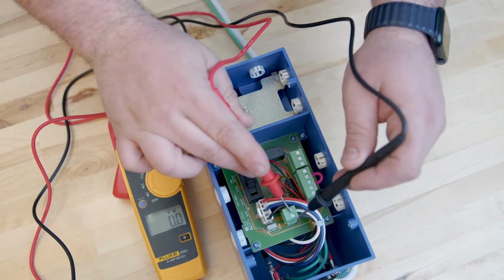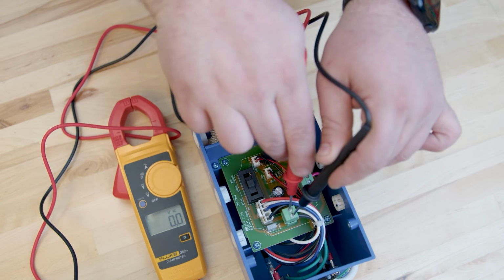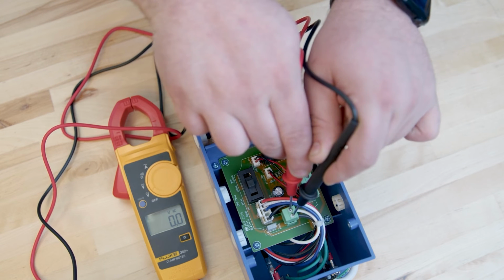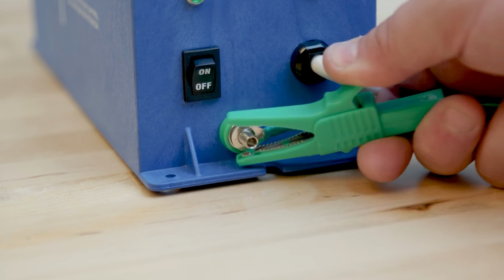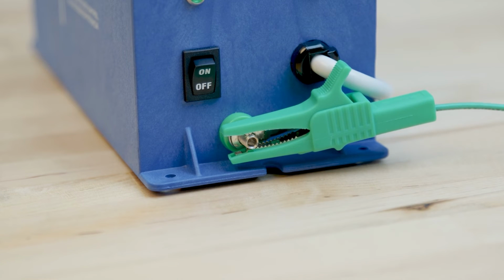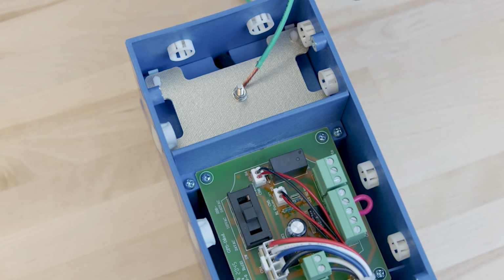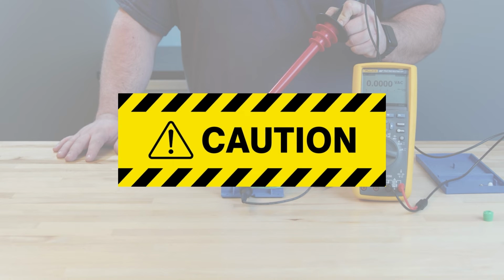If you do not have a high voltage probe, use a voltmeter to check the inline voltage on the control board. Attach a wire to ground and use the wire to discharge any voltage on the transformer. Only proceed when you have verified the power supply is de-energized.